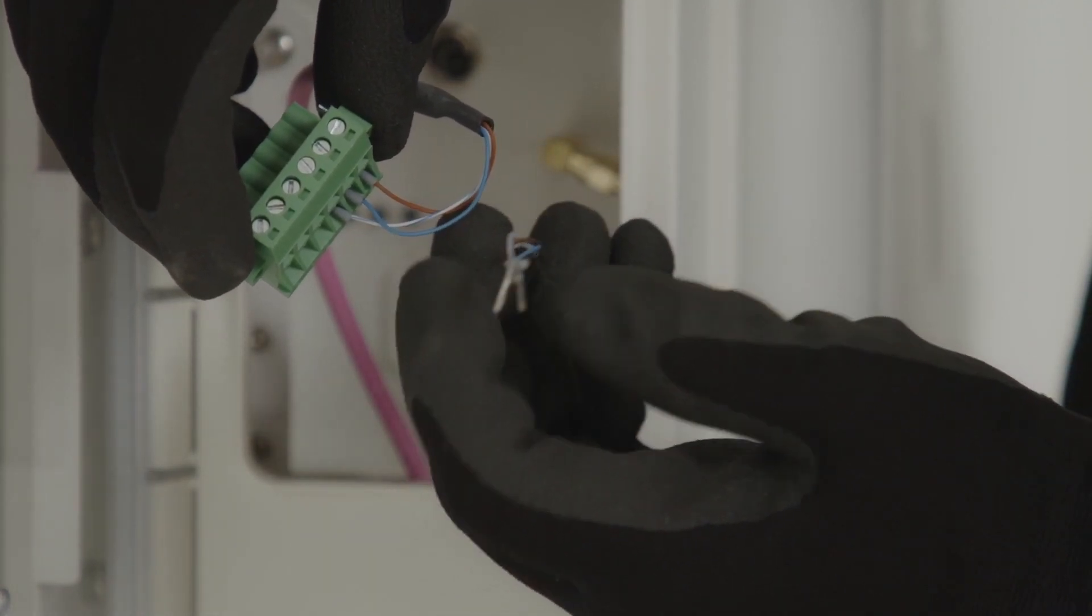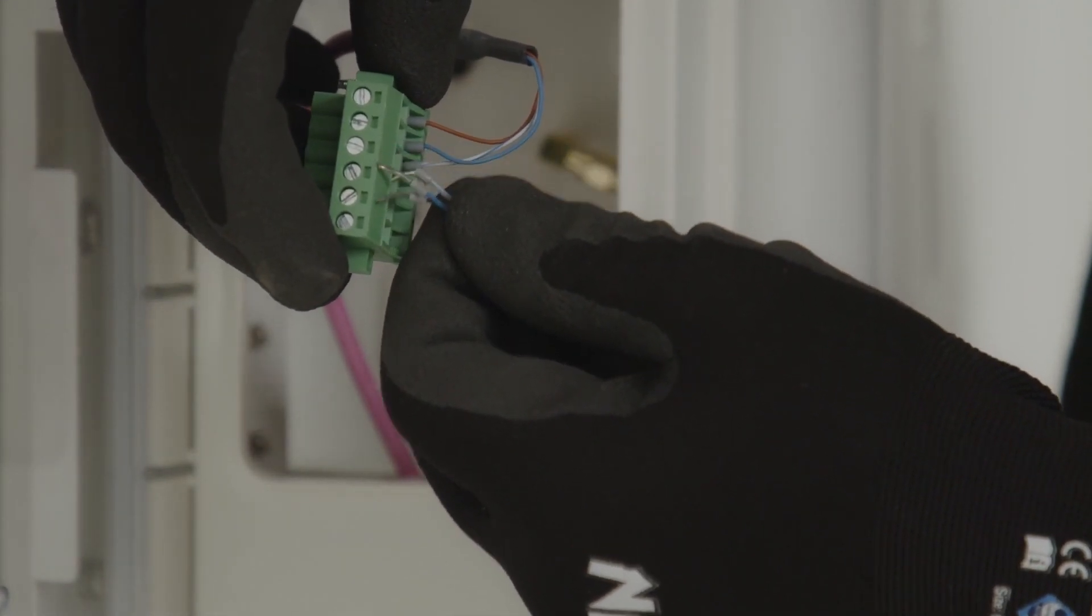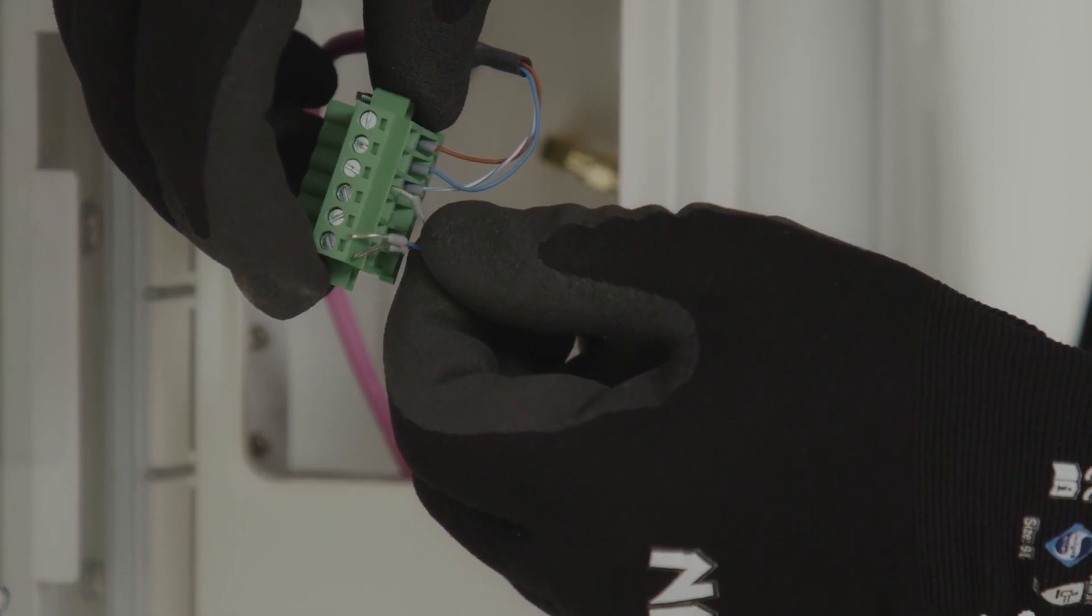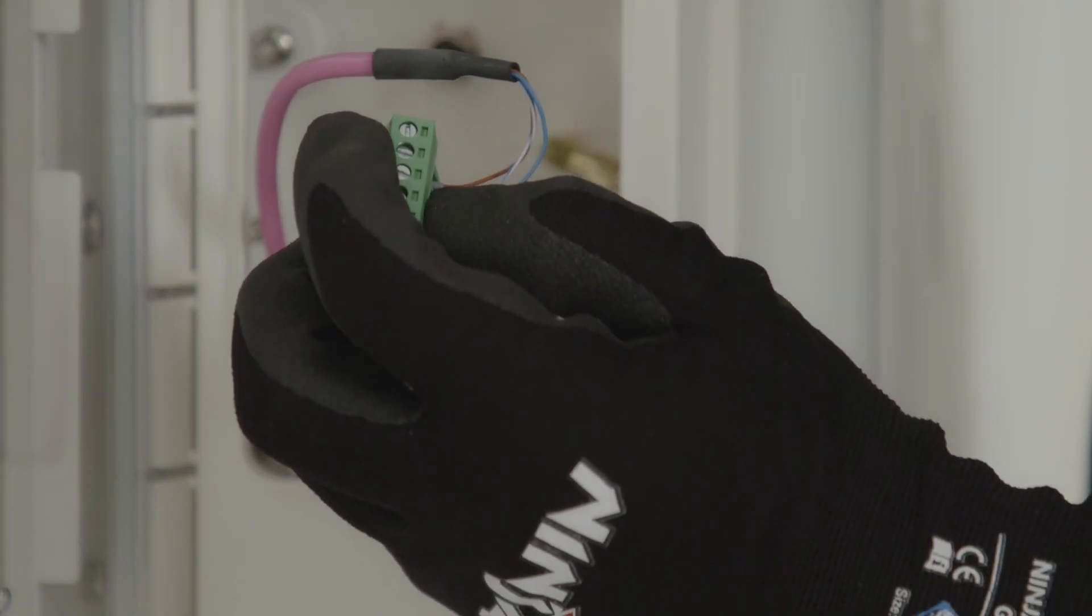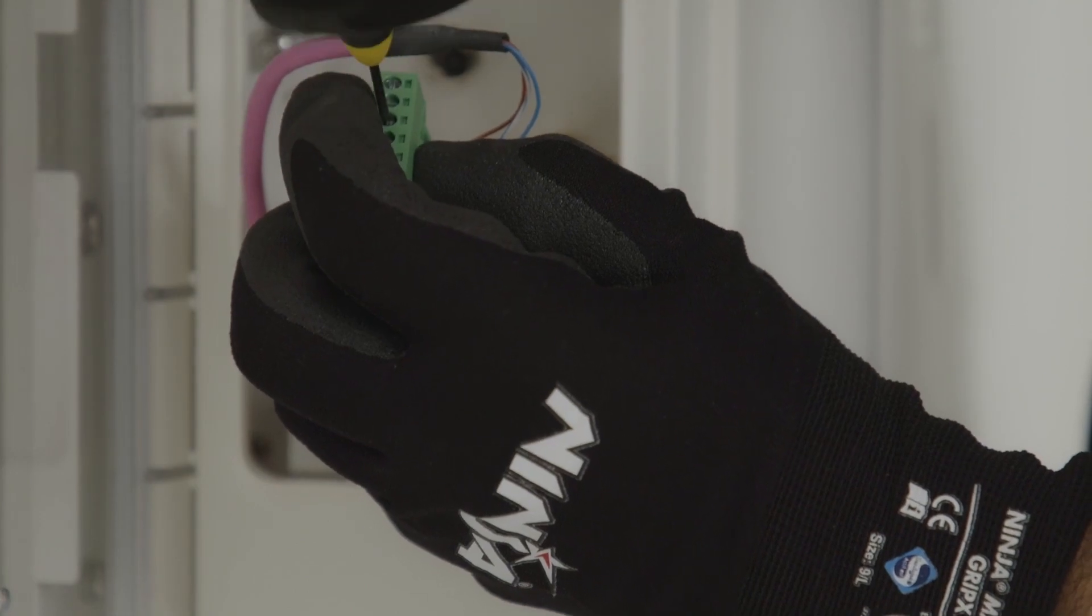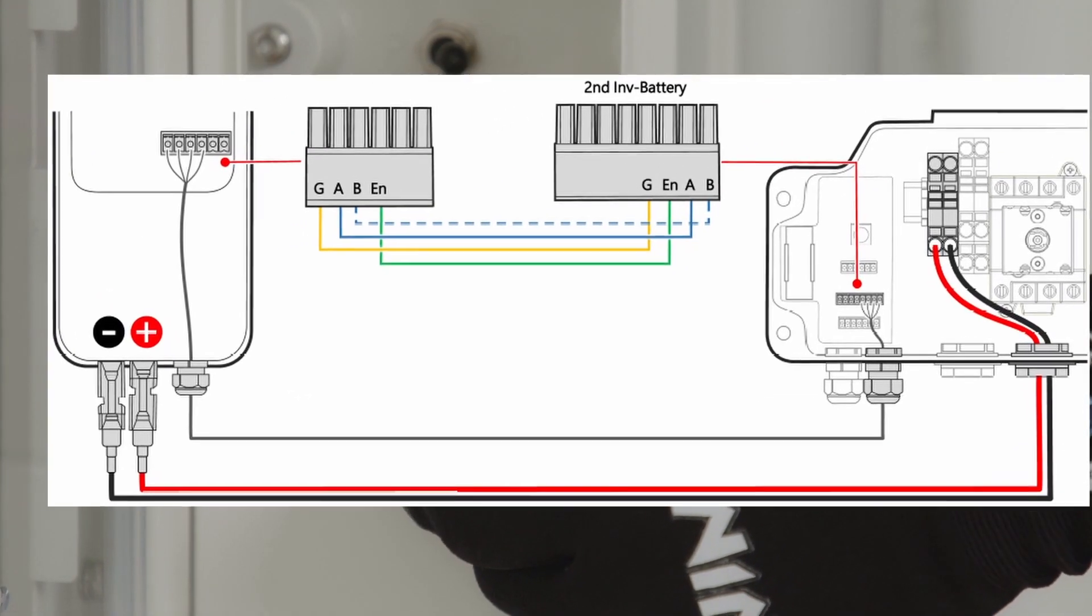If two SolarEdge batteries are being paralleled together, or three, the RS485 connection can be daisy-chained between each. As you'll see on the terminal block, there is an in and out connection for the RS485, so simply wire the adjacent SolarEdge home battery to the spare port on the terminal block.